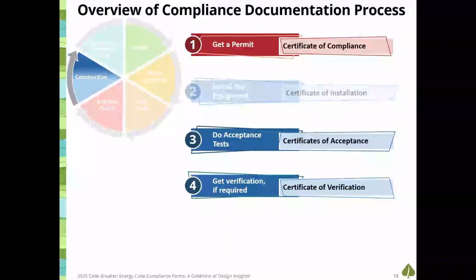I wrote up this whole note block. I said, put this in your drawing set that talks to the contractor about who they need to engage to do the acceptance testing and who they need to engage to do the verification testing. Verification testing must be done by a third party inspector not employed or related in any way to the installing contractor. That's not true for acceptance testing, it can be the contractor, they could be related to the contractor. They just need to be certified if it's mechanical and lighting equipment. I really tried to make sure the contractors knew before the end, make sure all of this is in place so everything can go smoothly for final.